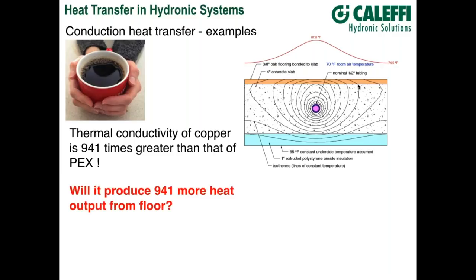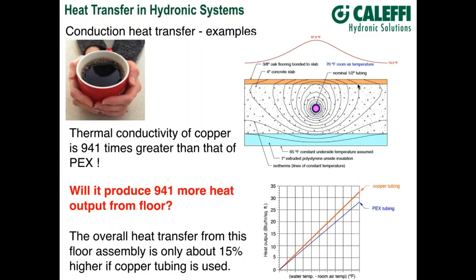The answer is no. Based on a finite element model, the copper tube does produce higher heat output — but only roughly about 15% higher. One question submitted prior to the webinar asked about the difference in heat transfer rate between PEX tubing and PEX-aluminum-PEX tubing. It's very, very small — literally on the order of maybe 1% better at most for the PEX-aluminum-PEX.